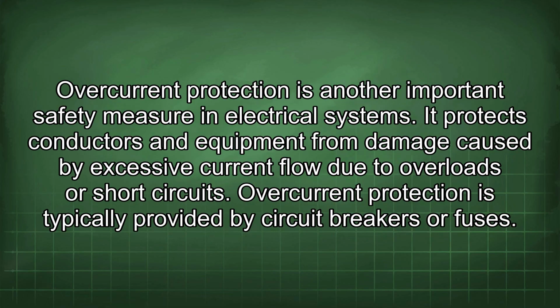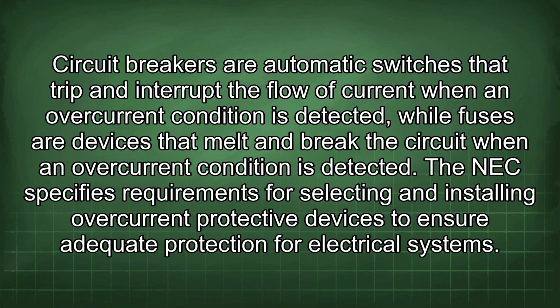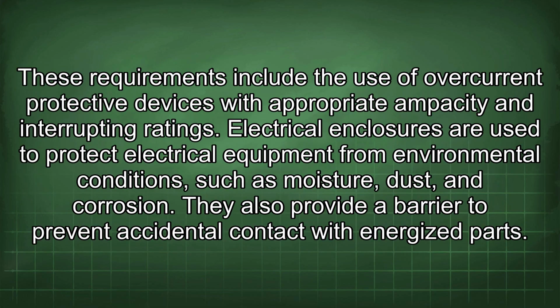Overcurrent protection is another important safety measure in electrical systems. It protects conductors and equipment from damage caused by excessive current flow due to overloads or short circuits. Overcurrent protection is typically provided by circuit breakers or fuses. Circuit breakers are automatic switches that trip and interrupt the flow of current when an overcurrent condition is detected, while fuses are devices that melt and break the circuit when an overcurrent condition is detected. The NEC specifies requirements for selecting and installing overcurrent protective devices to ensure adequate protection for electrical systems. These requirements include the use of overcurrent protective devices with appropriate ampacity and interrupting ratings.